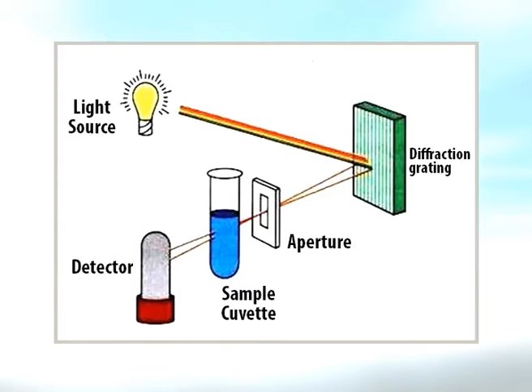Number third is the sample and reference cell. One of the two divided beams is passed through the sample solution and the second beam is passed through the reference solution. Both sample and reference solution are contained in the cells. These cells are made of either silica or quartz. Glass cannot be used for the cells as it also absorbs light in the UV region.